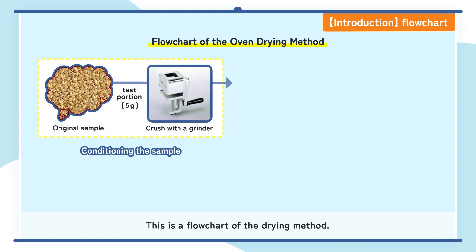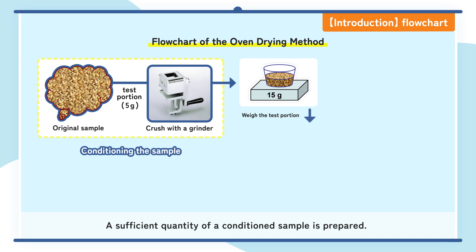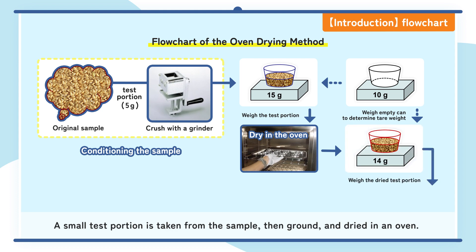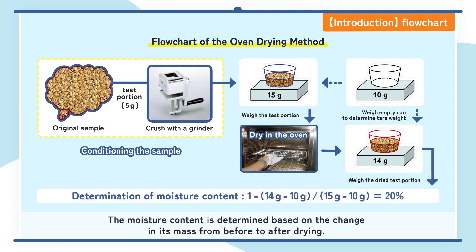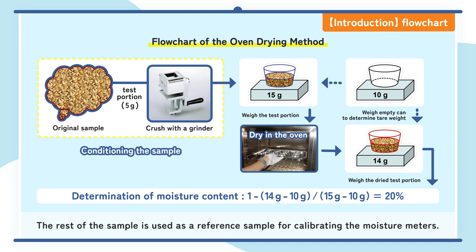This is a flow chart of the drying method. A sufficient quantity of a conditioned sample is prepared. A small test portion is taken from the sample, then ground and dried in an oven. The moisture content is determined based on the change in its mass from before to after drying. The rest of the sample is used as a reference sample for calibrating the moisture meters.